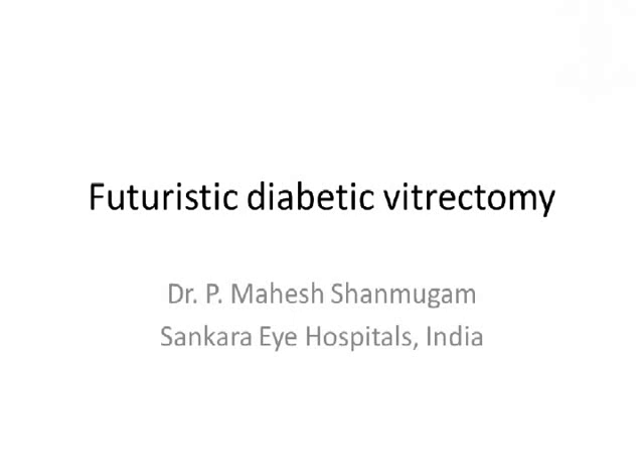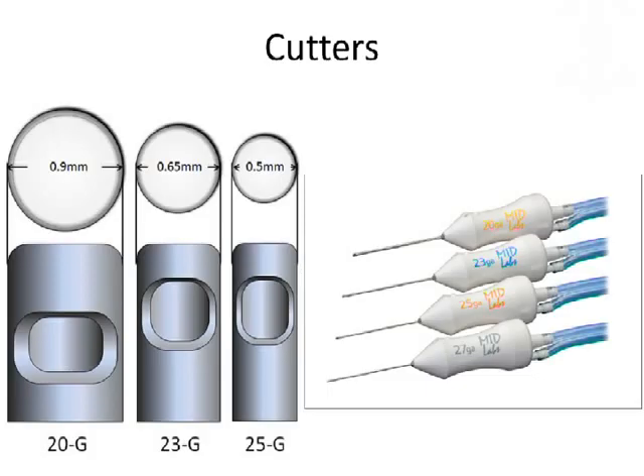We went through this: we started with 20 gauge, 23 gauge, 25 gauge, and now of course we have the 27 gauge. Pretty much 25 gauge is good enough for all the work which we are currently doing with the 23 gauge. I don't have too much experience with the 25 gauge because the equipment which I use does not support the 25 gauge. This is one of the very few gauges which I have done. So you can segment, you can bead, you can delaminate, pretty much do everything just with the cutter itself. So 27 gauge does probably about 80% of what you can do with the 25 gauge.